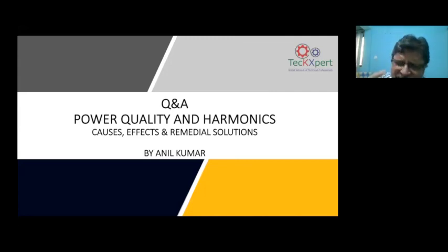Selecting thyristor switching, you need to do a bit more detailing. I would certainly say that it is not the thing to simply go for thyristor switching. One has to see whether thyristor switching is really going to improve the average power factor and whether it is really needed for the load, if the load is fluctuating fast. For example, a welding load. Welding is a highly fluctuating load. There thyristor switching makes sense. But if you go and put thyristor switching for a compressor, it doesn't make any sense, because once it is at a given speed, it will just run at that speed. It does not keep changing the load. So there a contactor is enough, that's the answer.